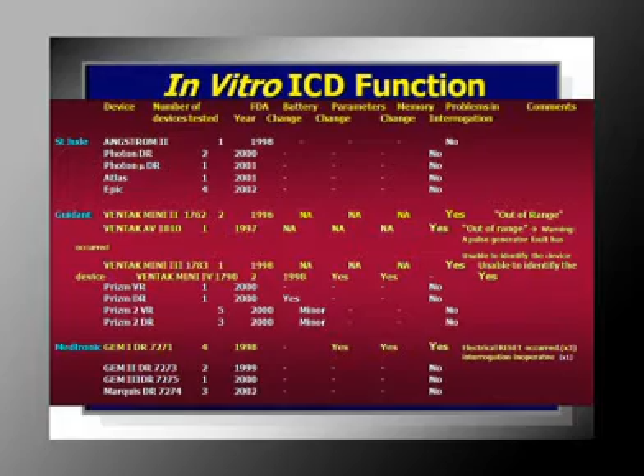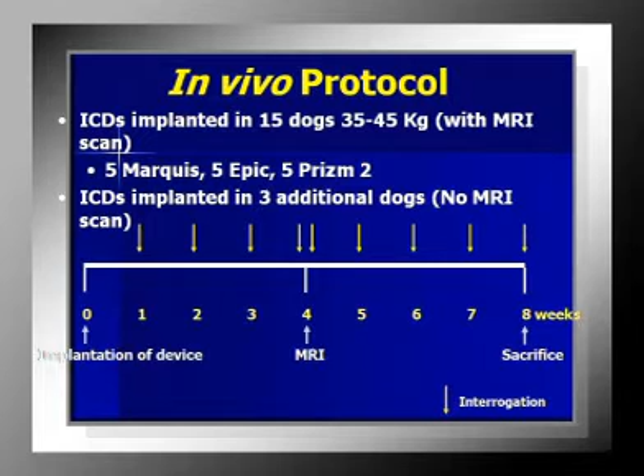And then Ariel did this study where we implanted devices at time 0, interrogated them every week, did a lot of MR imaging, and then interrogated them every week after that, and then sacrificed them at 2 months. And the pacing thresholds actually increased at all pulse widths up to 4 weeks. Then we did MR imaging right here for 3 hours at very high power. And then the pacing thresholds actually decreased. So the message here, you could interpret it as MRI should be done on everybody to reduce their threshold. Obviously, this was just a happy coincidence because this is kind of the normal evolution of the capture threshold, but at least the MRI did not seem to hurt it.